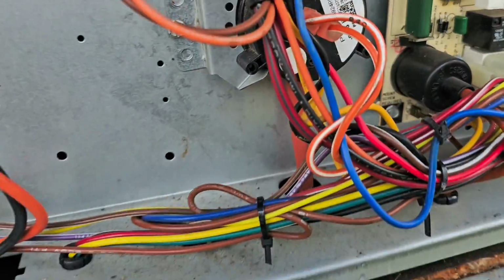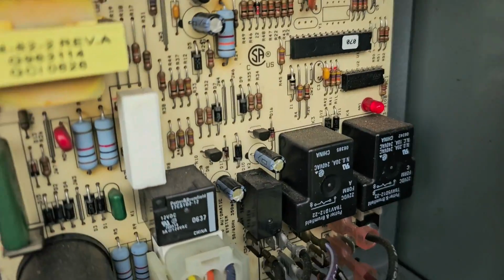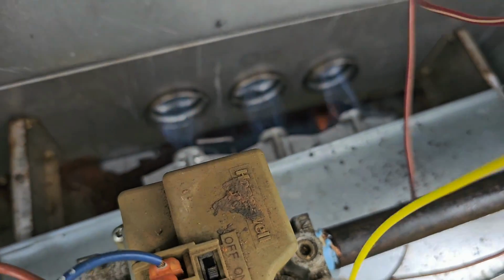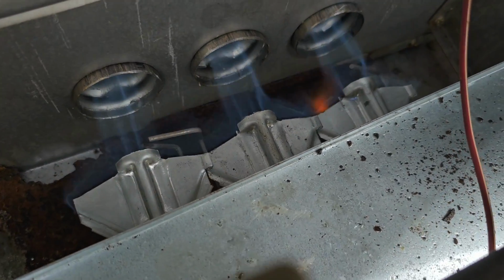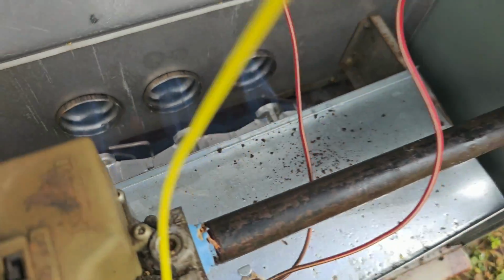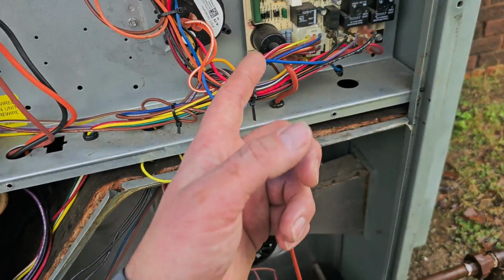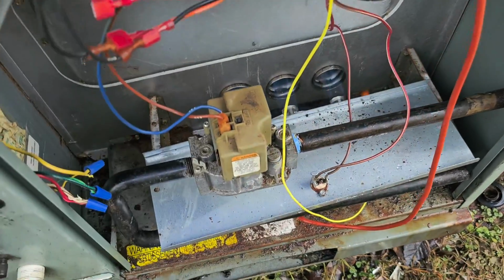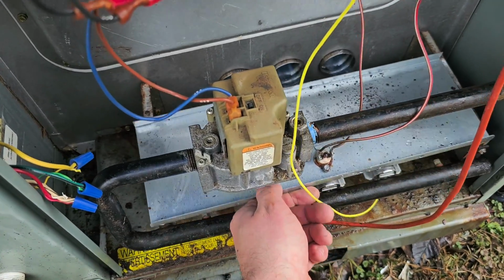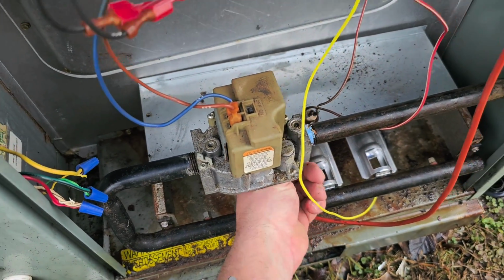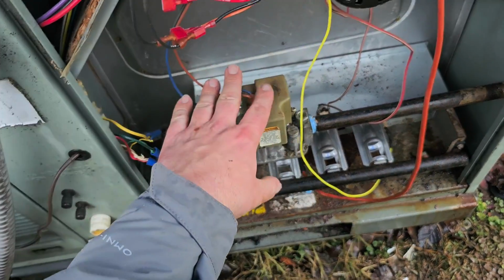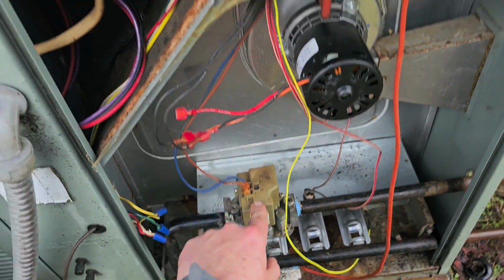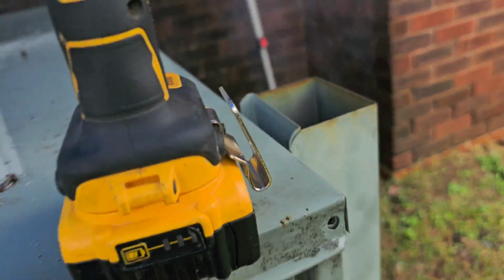Inducer motor's running. Pressure switch is closed. No fault code on the board. There it goes. Sparks. Ignites. Flame sensor picks up the signal. Flame rectification happens. Blower motor should run. And now we've got heat. If you want to know how to set gas pressure, I'll put a video down below so you can learn how. And there's the smoke.